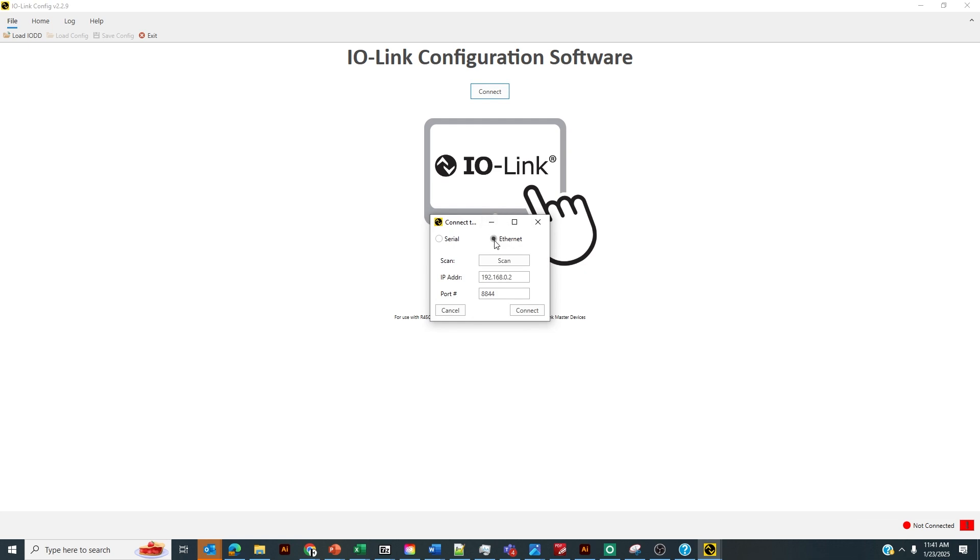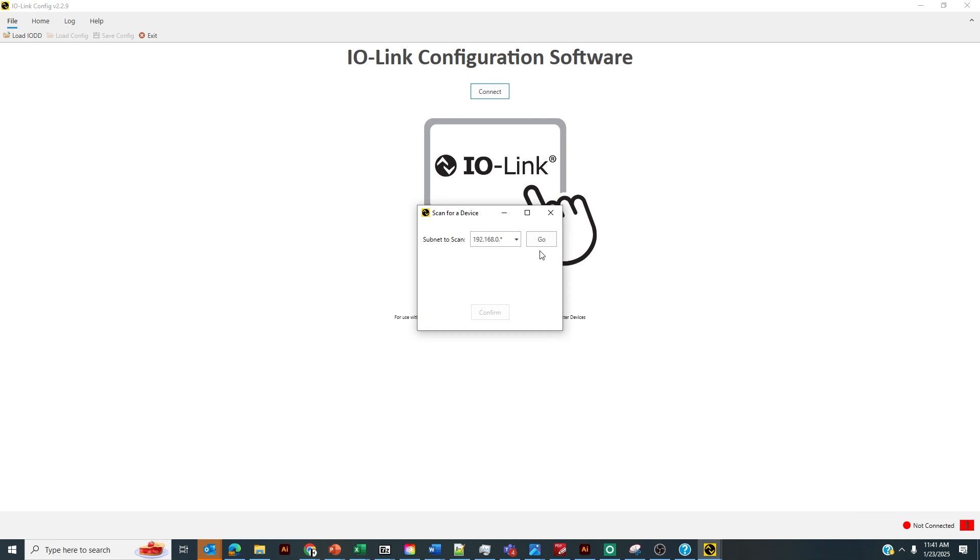We're going to select Ethernet as we're connected to an Ethernet IO-Link Master and then we're going to hit scan. The subnet to scan will be 192.168.0 as this is the default IP address of the device. Out of the box, the DXM R90 4K has an IP address of 192.168.0.1. Then let's click go.